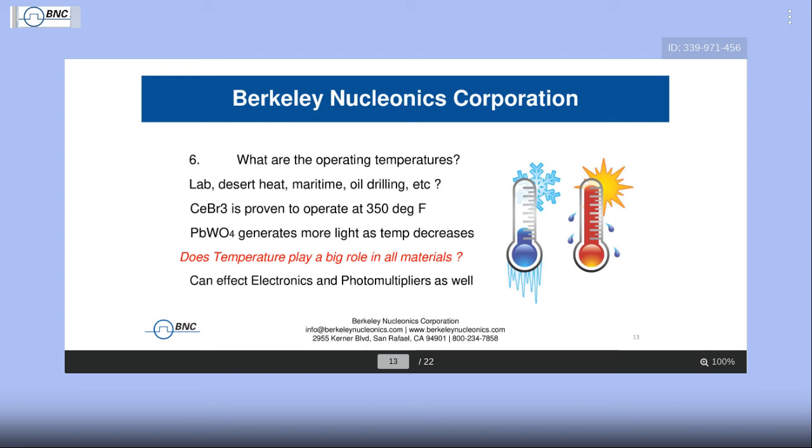And so if you're going to be exposing the detector that you're choosing to various environments, particularly if you're mobile, handheld, or vehicle, then you want to make sure that you have a way of adjusting, of recalibrating, of stabilizing your measuring points while you move from one temperature extreme to another. It's very important that you take that into consideration when you're planning.